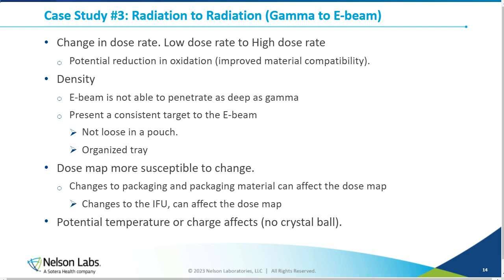The other thing is we are going to need a new dose map. With that dose map, as we mentioned, we're going to be susceptible to changes due to density. So things such as adding IFUs, thickening the IFU, changing our carton density, those are all things that are potentially going to affect an E-beam and how well it can sterilize the product, as well as your dose range. So changes that we're going to need to consider with sterilization are going to be that density.